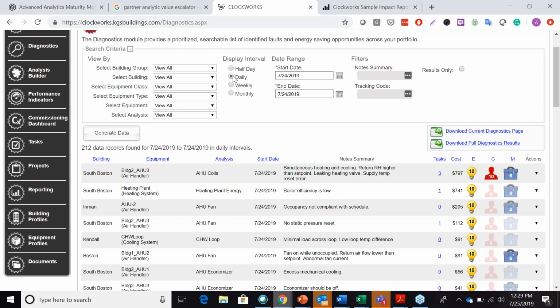The reason for that is this does not replace any critical alarming that you already have in your building automation system. We don't want to know that a valve's been leaking for 5 minutes. We want to know that it's been leaking when it reaches a threshold that it's really worth our time and attention, and that it's more or less important than the other range of possible conditions that are happening on campus that we want to draw our team's attention to.